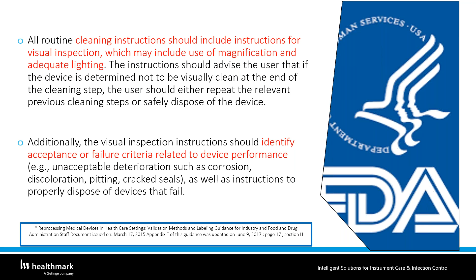In March of 2015, FDA sent out guidance for manufacturers of devices that the cleaning instructions should include visual inspection of most cannulated items, including borescopic inspection. Additionally, the visual inspection should identify acceptance or failure criteria. For example, if you see a little bit of rust, is that acceptable, or should you remove it? What should you do about pitting or cracks? That is what FDA wanted.